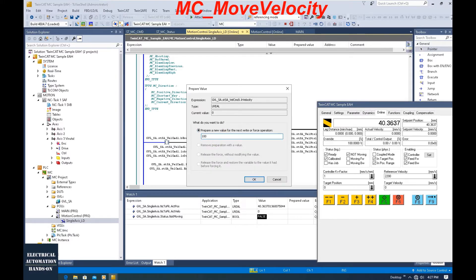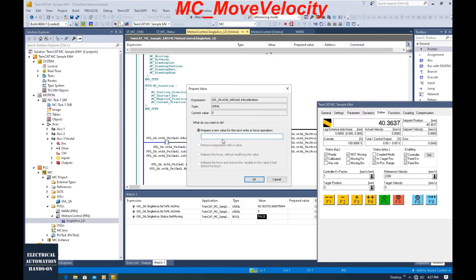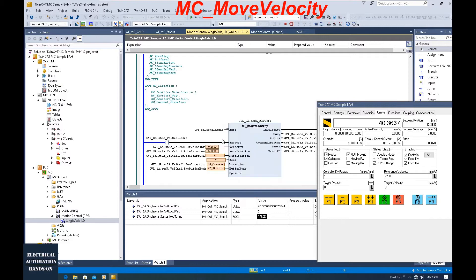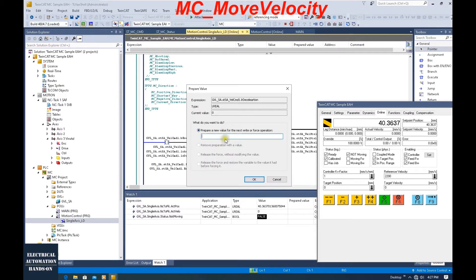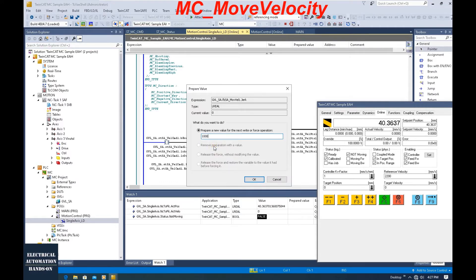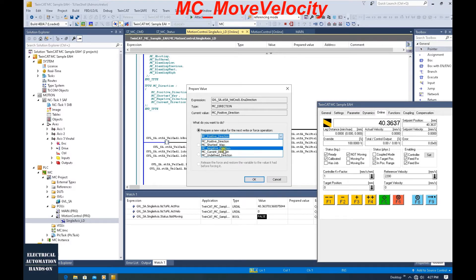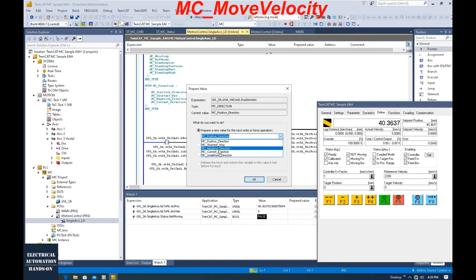Let's set the velocity command here — for example, 100 millimeters per second. This acceleration, let's set 500. The deceleration, let's set 500. And jerk, we can set 1000. For direction, by default we can select from here. The value: the first one is number one, that's positive. Keep in mind, the negative direction command is number three — not number two. One, two, three: three means negative.